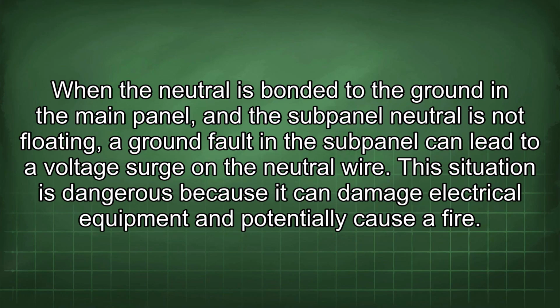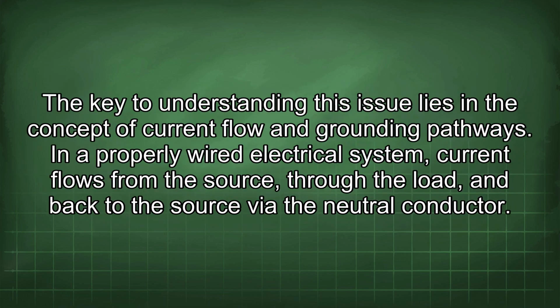When the neutral is bonded to the ground in the main panel and the subpanel neutral is not floating, a ground fault in the subpanel can lead to a voltage surge on the neutral wire. This situation is dangerous because it can damage electrical equipment and potentially cause a fire. A key to understanding this issue lies in the concept of current flow and grounding pathways.